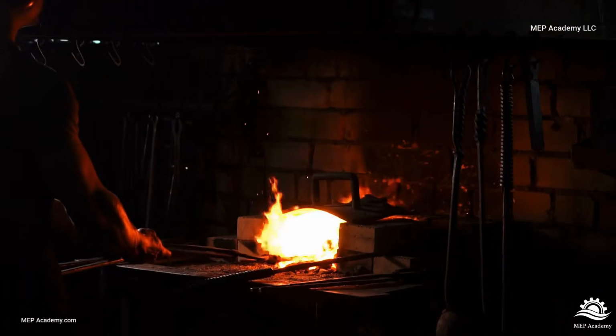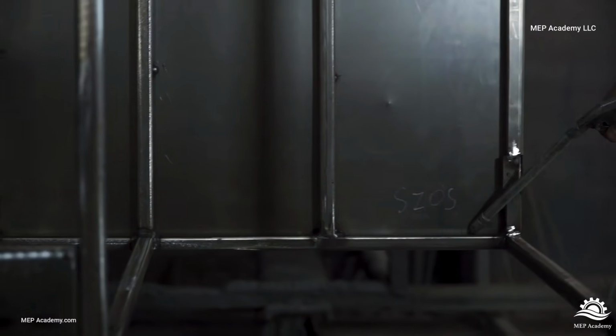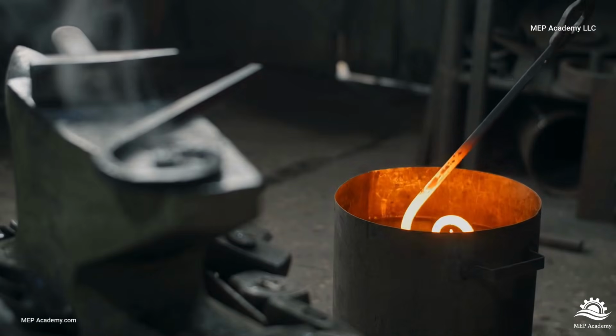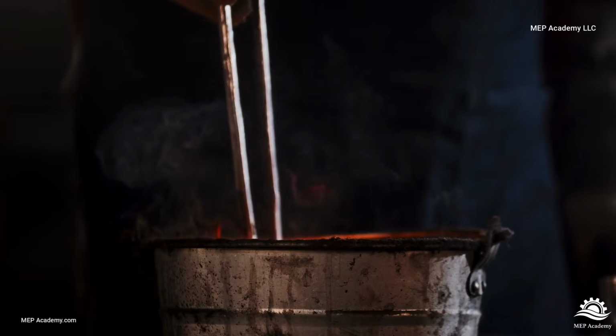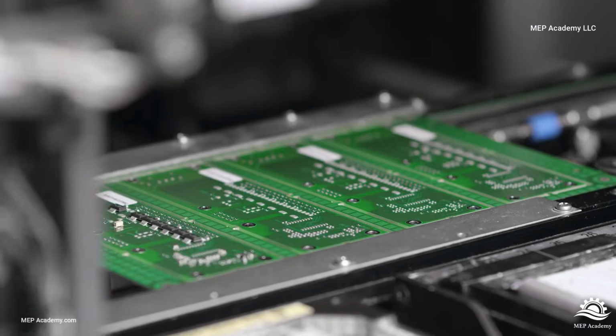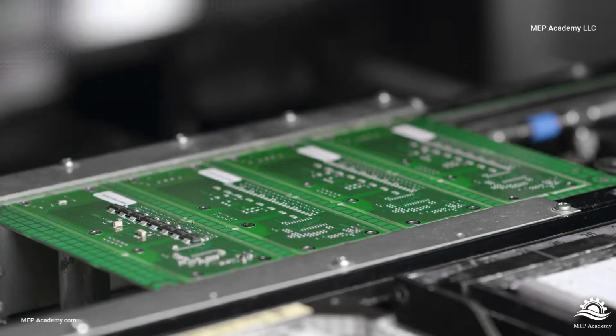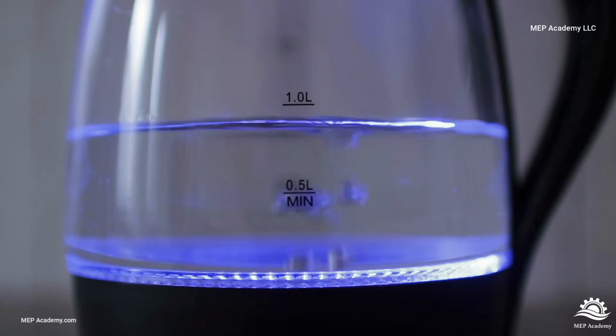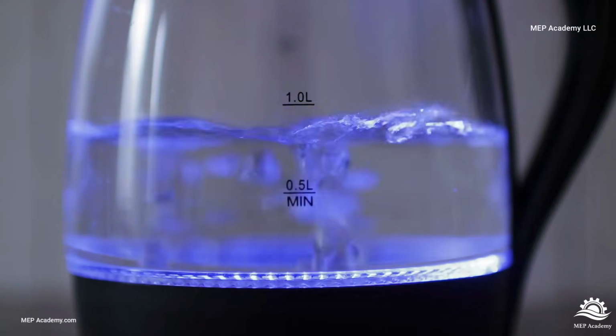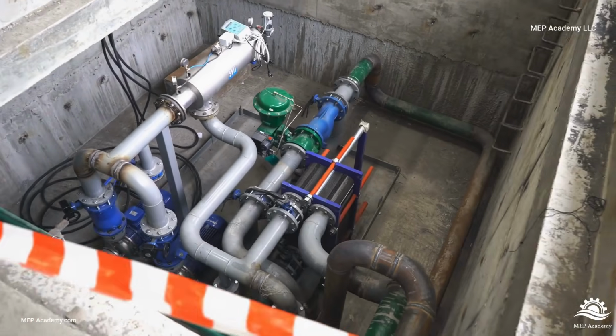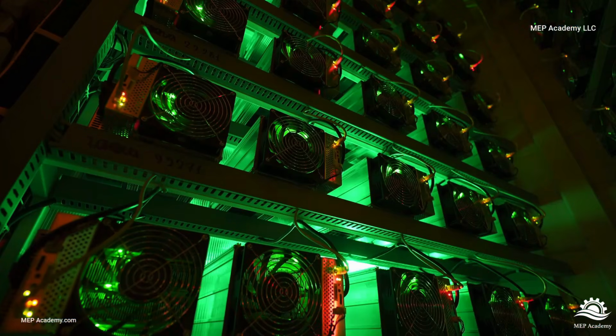Think about trying to cool a red-hot piece of metal. You could blow air across it, or you could place it in water. The water removes heat dramatically faster. The same principle applies inside an AI server. Water can absorb significantly more heat than air. This allows cooling systems to remove large amounts of heat using much smaller volumes of fluid. That's why the industry is increasingly turning to liquid cooling.